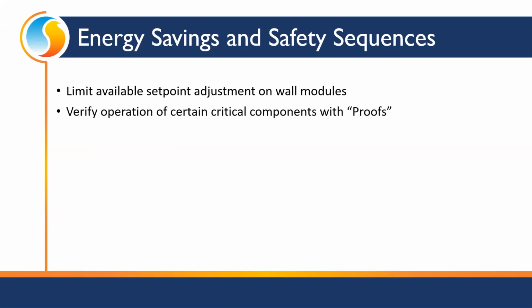We can verify operation of certain critical components with proofs. Like we want to make sure that our fan is running in the equipment before we start trying to heat or cool, or we want to make sure that pumps are turned on before we try to fire boilers or chillers. So we're going to verify that operation. We can also apply high and low temperature limits if stuff starts getting too warm or too cold, where we could be approaching the point of doing some damage. We can shut stuff down and back things off.